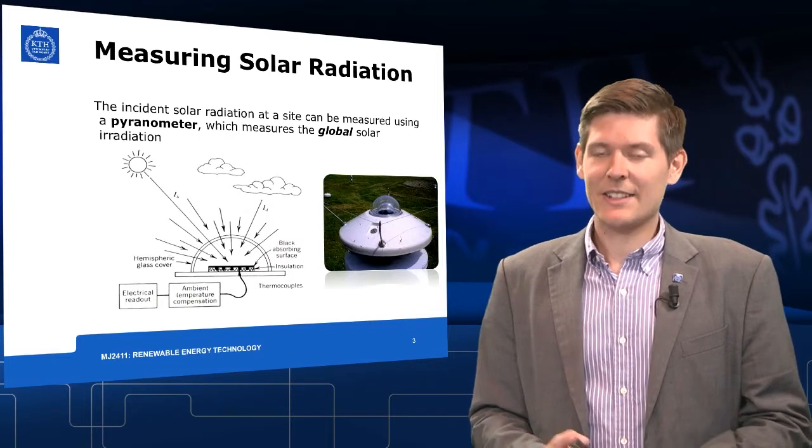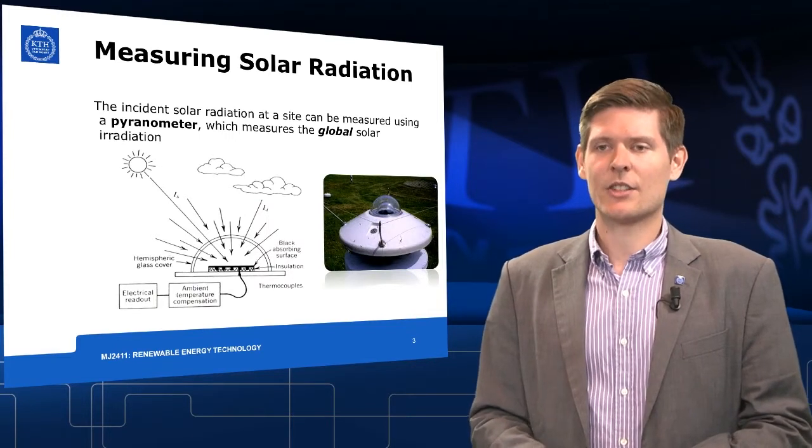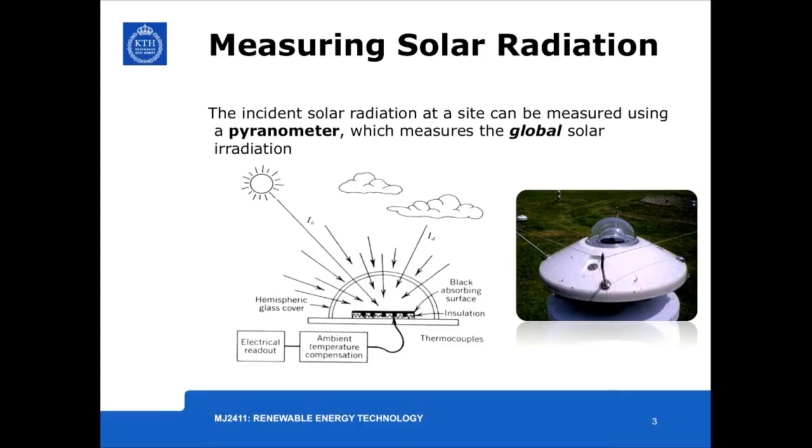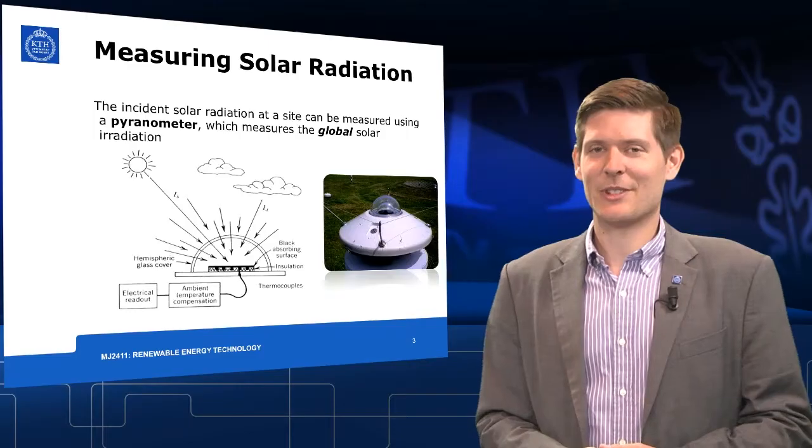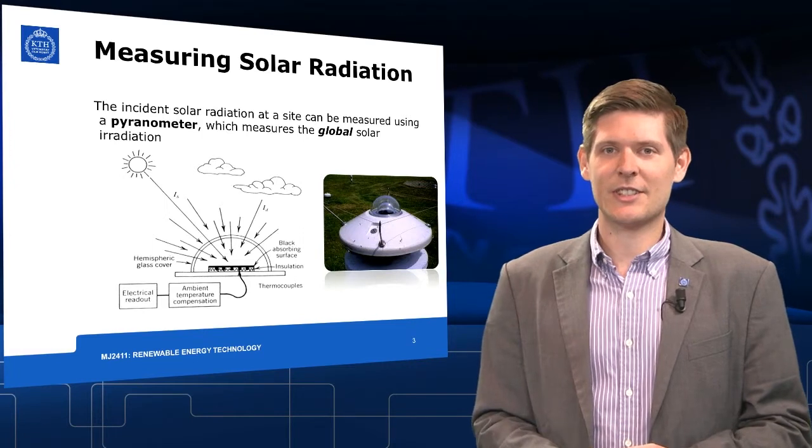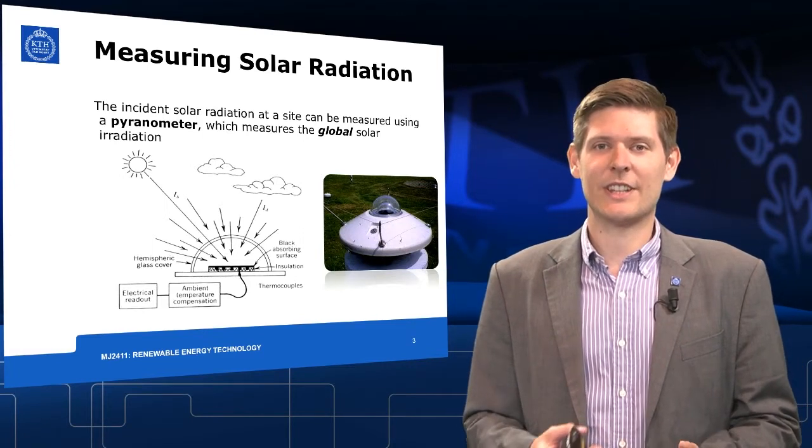A device which is able to measure the incident radiation, the total or global incident radiation is the pyranometer. Within this device, an absorbing surface is shielded from heat losses and connected to thermocouples. Depending on the incident flux, the temperature which is reached at the surface is proportional to the incident flux.